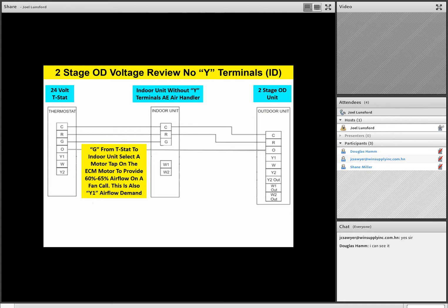Now here's how this happens. What's going to happen is that the contractor, when he sets this up, if he has an AE air handler, he's going to set up his G airflow. In other words, when you get a G call from the thermostat for the indoor fan to come on, that fan speed has to be 60 to 65% airflow. So when I get a fan call, it's going to drive that fan to 60 to 65% airflow. And by the way, this is also the Y1 airflow demand.